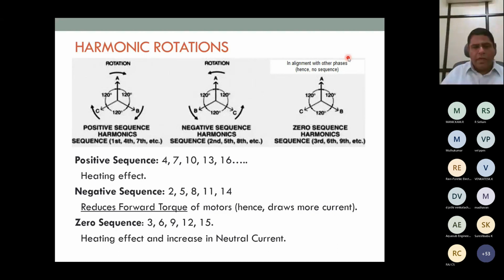These have only a heating effect, but a negative sequence such as 2, 5, 8, 11, 14 and so on reduces the torque of the motor. So what happens is the motor has to draw more current to maintain its RPM, thereby your power consumption goes up.